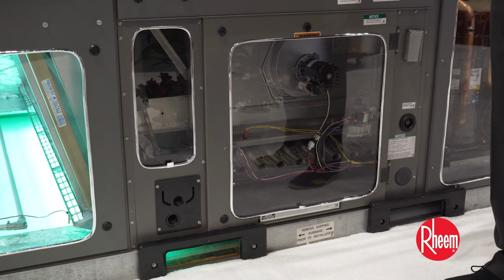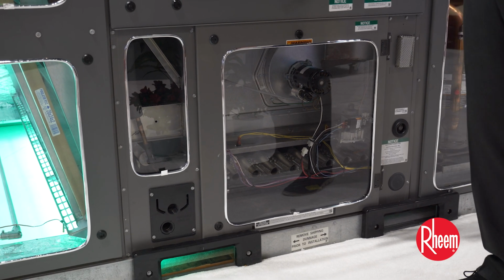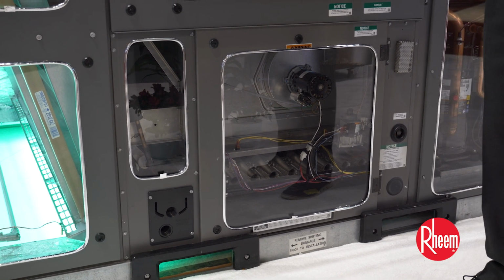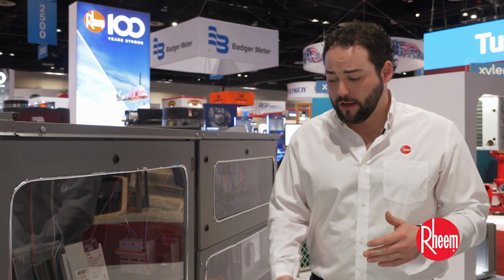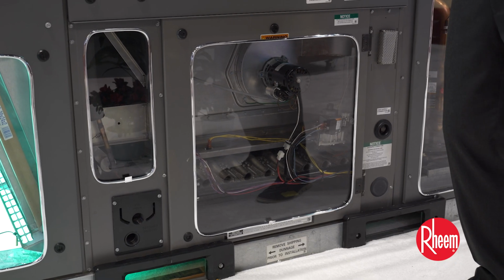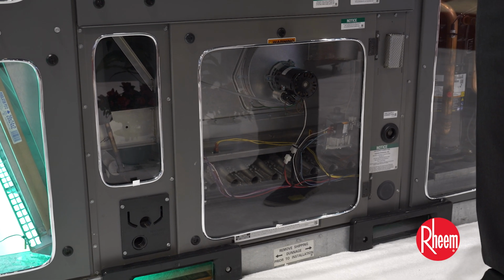What you'll see here is our slide out drain pan. It can either be P-trapped out the side or run through the base as standard. You can quickly clean it out, put it right back in, and it slides right out under the evaporator coil. It does come with a built-in factory installed float switch, 300 ohms to ground, so you don't have to worry about using a third-party float switch within the unit.